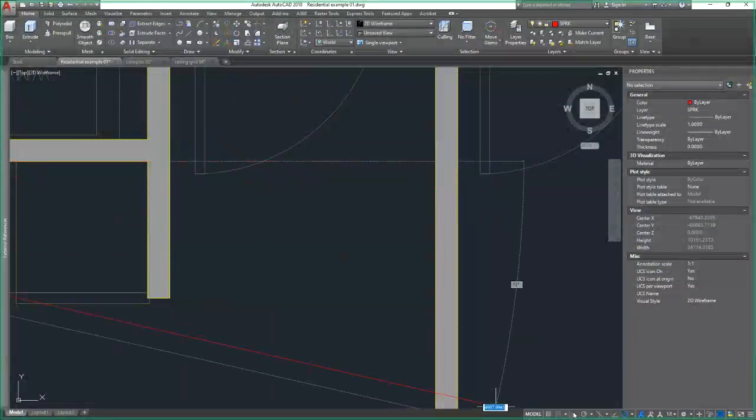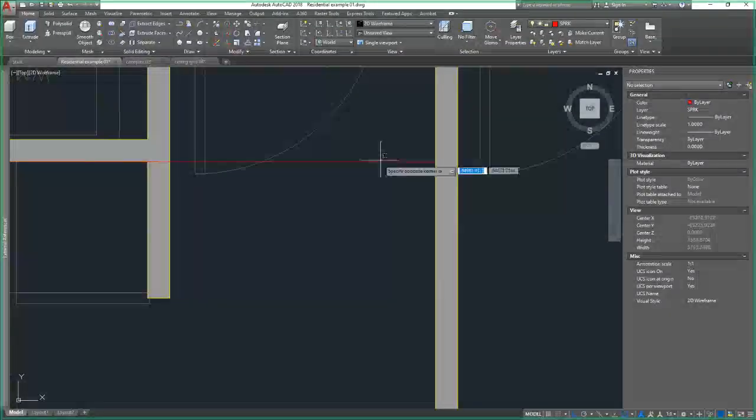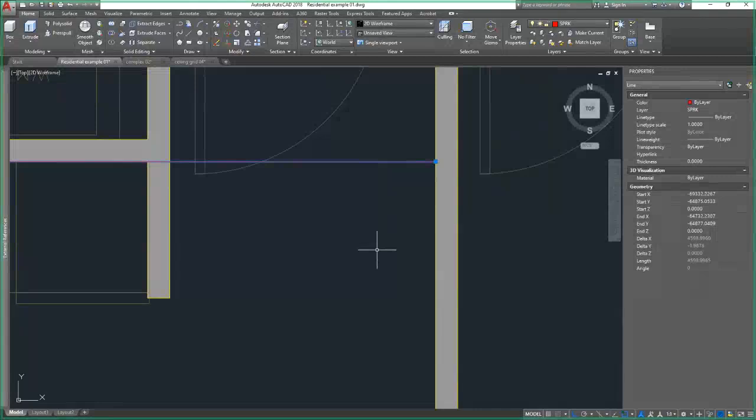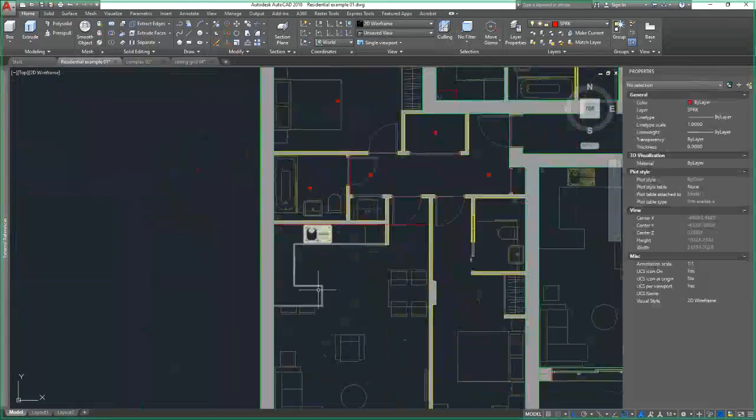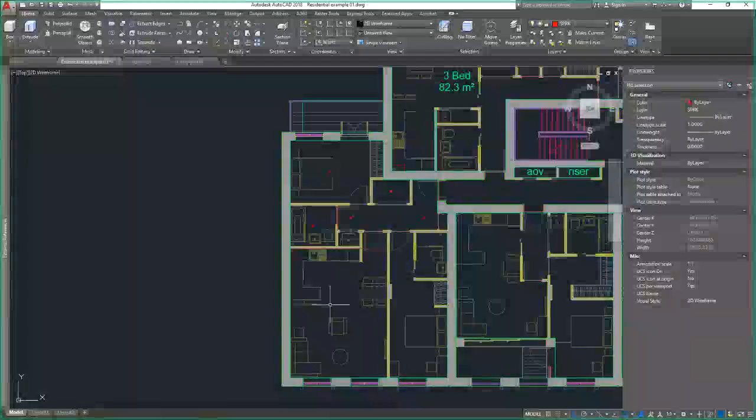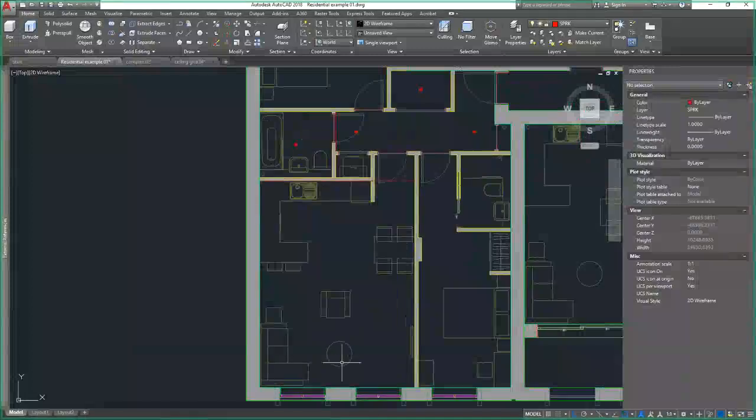I'll get this right. Width is 4.6. It's basically 4.6 exactly. So that is actually too much, because 4.5 is the maximum distance that I can have with one sprinkler head on that run.